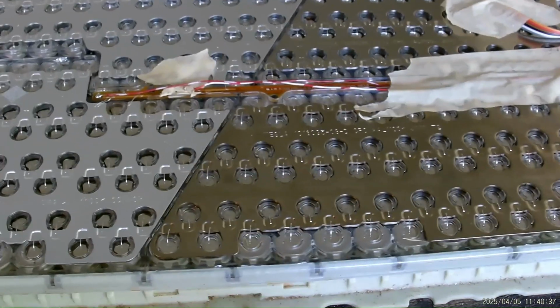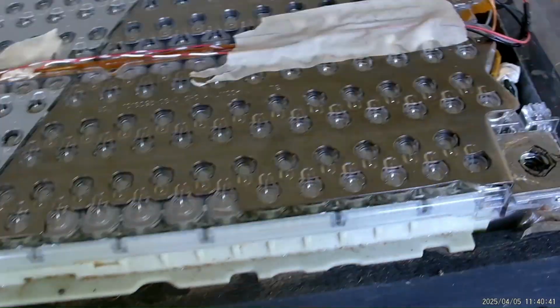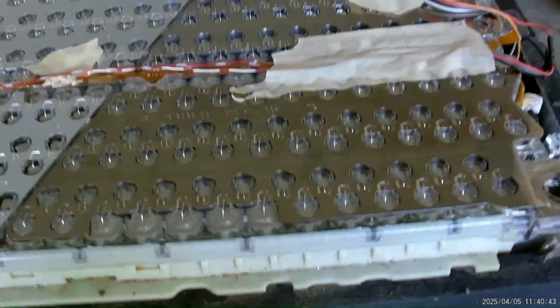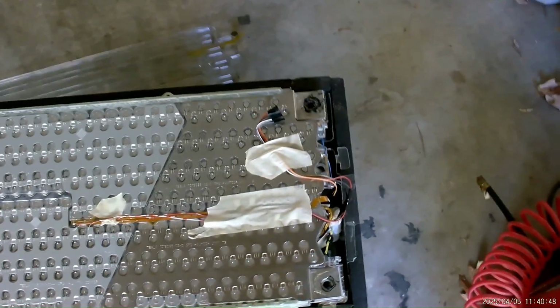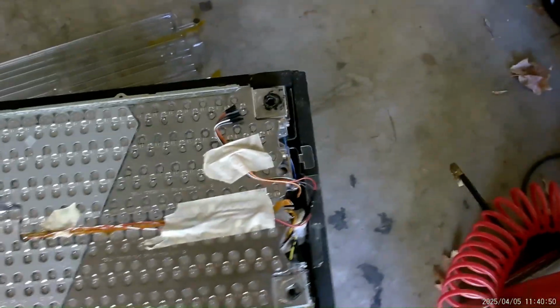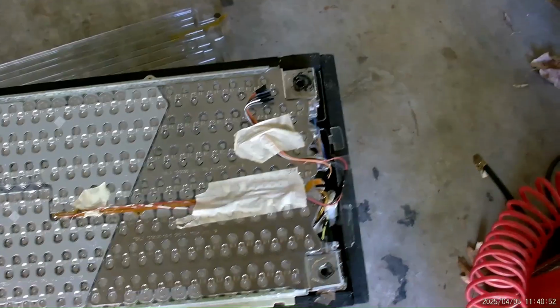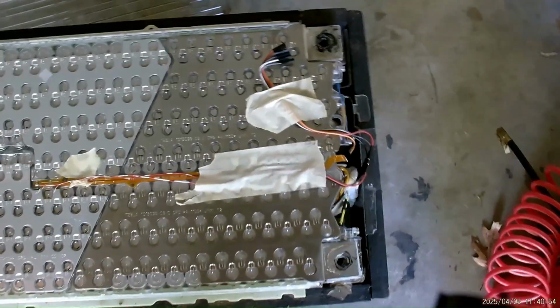Now, this module is a 24-volt module. The cart is made for 48 volts. So I need 2 of these modules in series to give me 48 volts. Each module has 6 banks consisting of 74 cells in parallel.